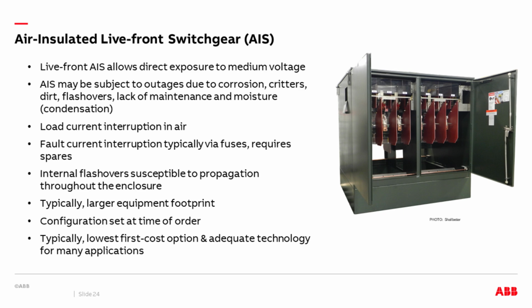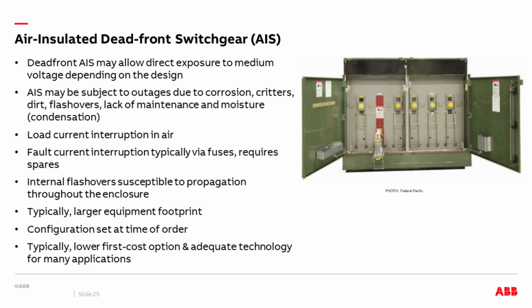The fault current interruption is usually with fuses, and you need spares for the fuses. And because there's air, there could be something bridging the gaps, phase to phase or phase to ground, if critters can get in. If there's corrosion or high humidity, these things can reduce the insulating characteristics. But in general, there's quite a bit of air-insulated gear. It's typically the lowest first cost option, and it's perfectly adequate for many applications.